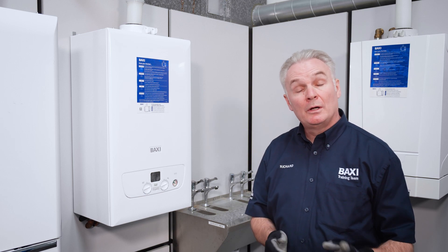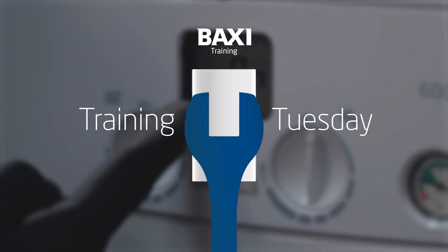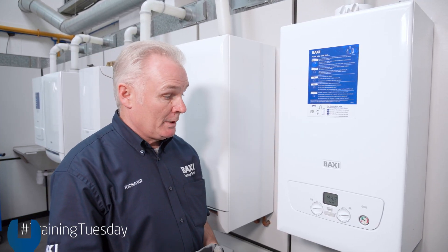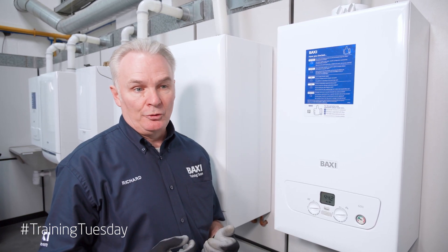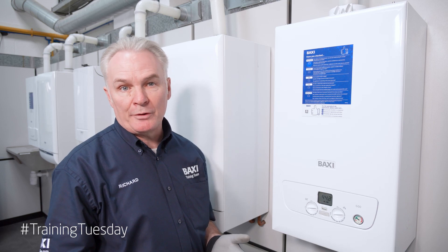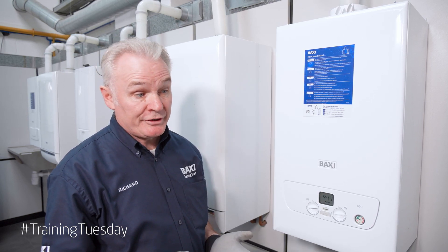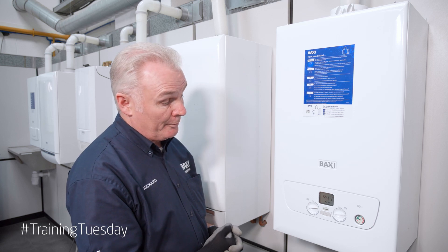Chimney sweep mode. If we're attending site for a Baxi 600-800 combination boiler and we want to put the unit into a commissioning mode so that we can do inlet working pressures, gas rates or a combustion analysis, we can do that through the control knobs on the fascia on the front of the boiler.